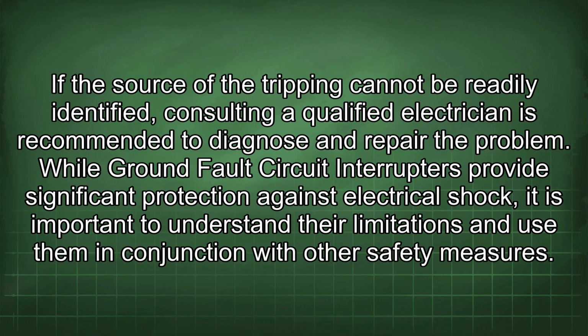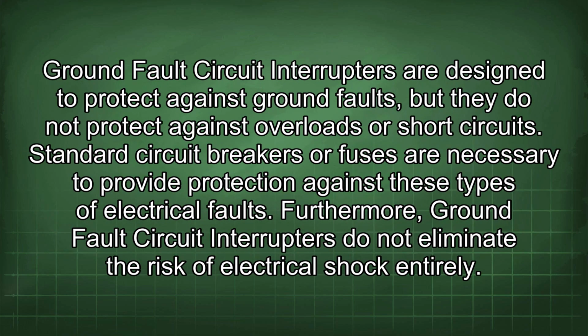If the source of the tripping cannot be readily identified, consulting a qualified electrician is recommended to diagnose and repair the problem. While ground fault circuit interrupters provide significant protection against electrical shock, it is important to understand their limitations and use them in conjunction with other safety measures. Ground fault circuit interrupters are designed to protect against ground faults, but they do not protect against overloads or short circuits. Standard circuit breakers or fuses are necessary to provide protection against these types of electrical faults.